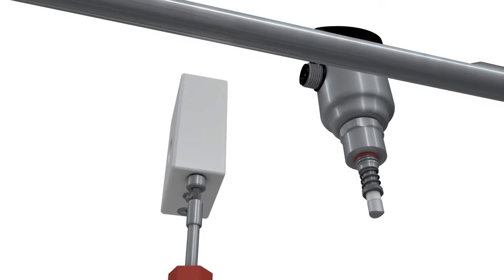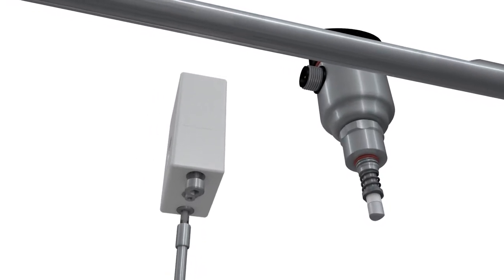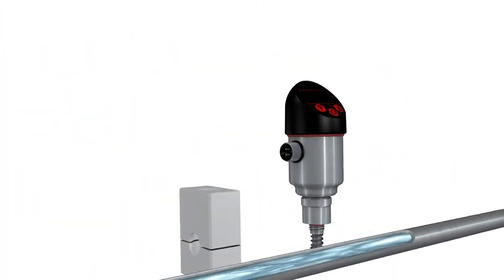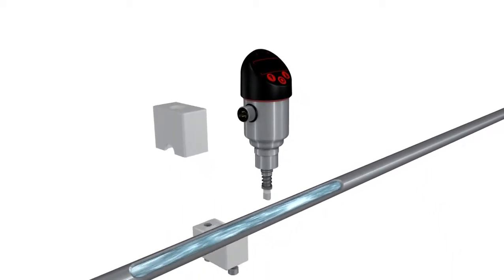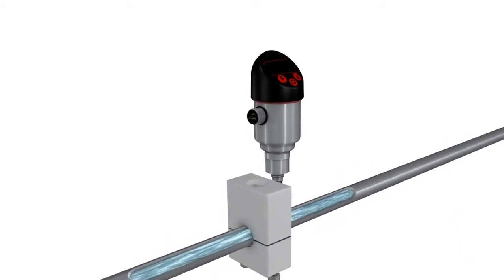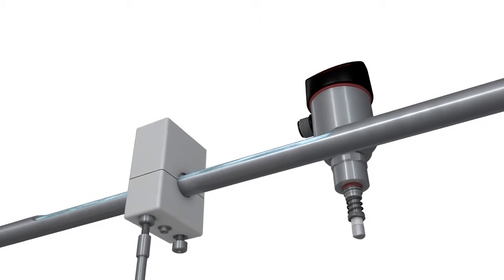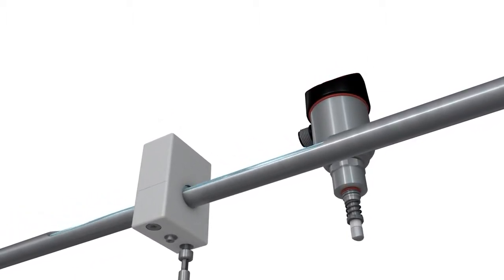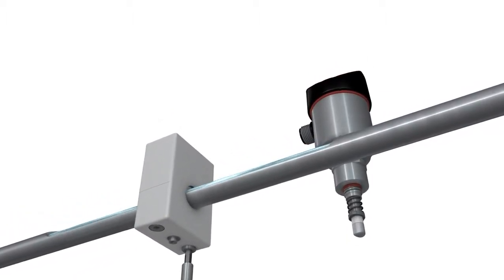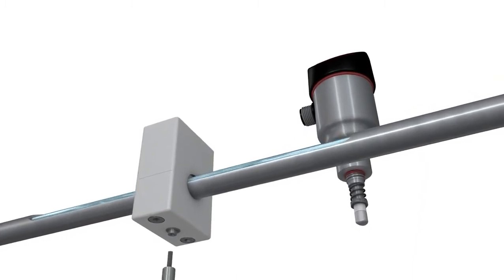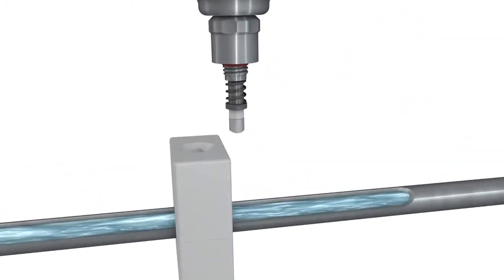We will now show you how easy it is to mount the sensor on the length of pipe. The clamp block is opened. The device is placed on the pipe and the block is closed with a few screws. The device clamps the pipe with a defined contact force. No welding is needed and plant production doesn't stop.